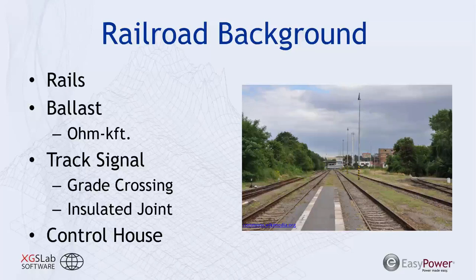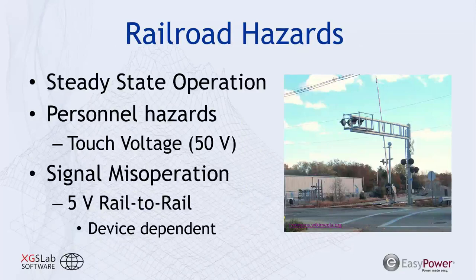And that could be located out on the rail itself or within the control house where all the control cables are brought in. And I mentioned that 50 volt value difference because in a steady state operation of a transmission line, the typical value that we're looking at from a touch voltage perspective or personal safety is 50 volts, and that's in line with OSHA. Again, we have equipment or signaling concerns in steady state operation with the signaling controls.